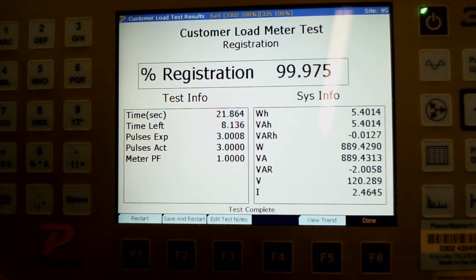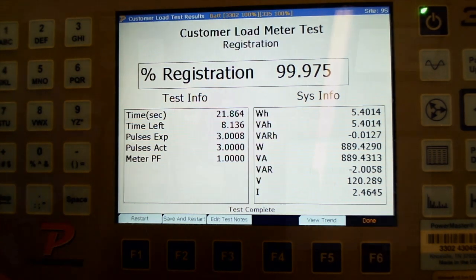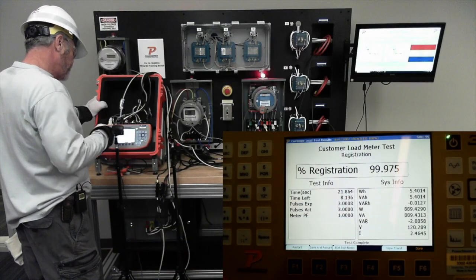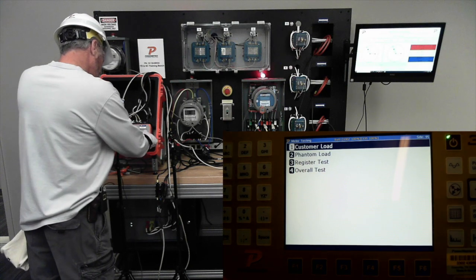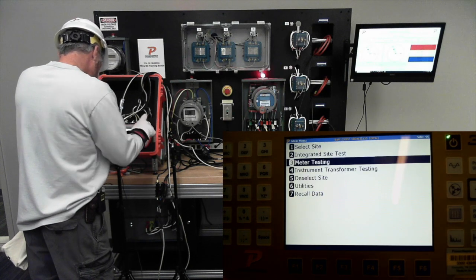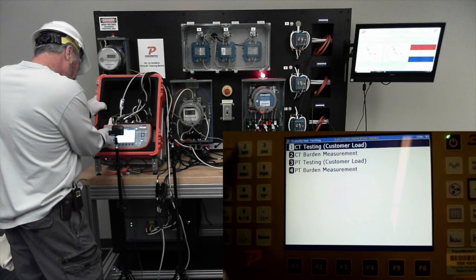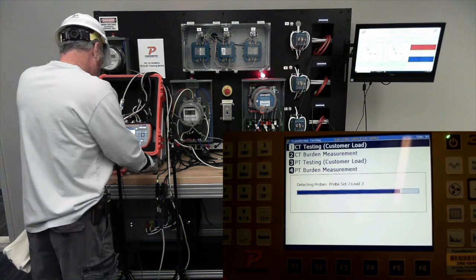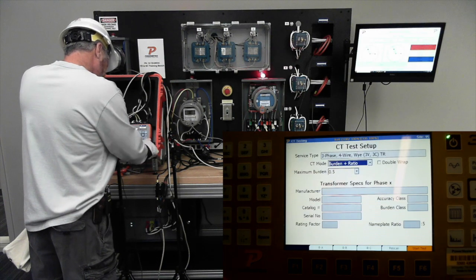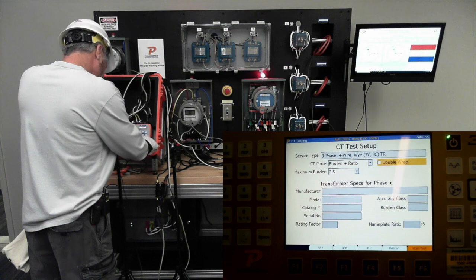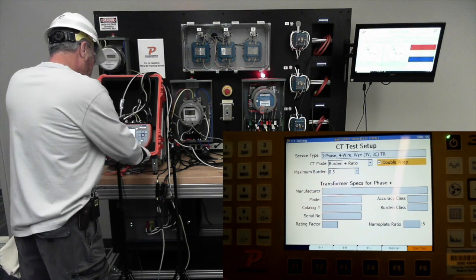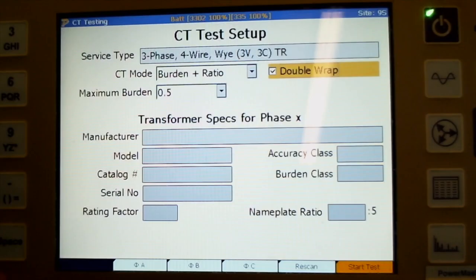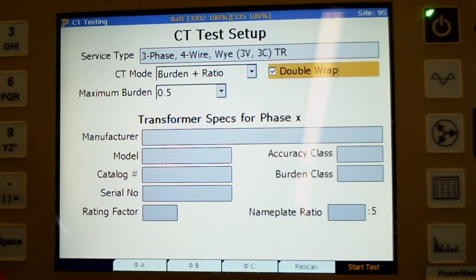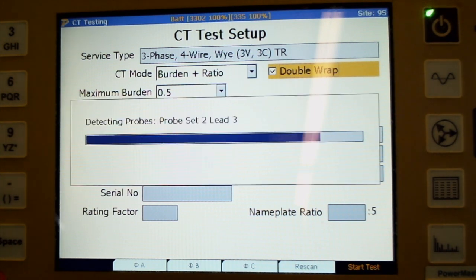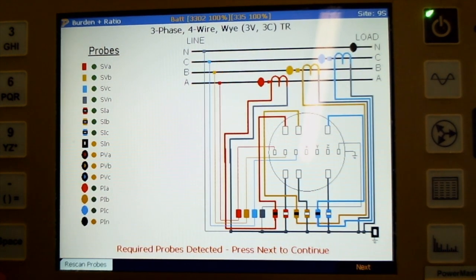All right, then we'll test our CTs real quick, and then we'll put an error scenario on there. It's one of the ones I like because it lets you use more functions on the test kit. So let's go to... make sure you check the double wrap box, right? Because I've got them double wrapped, or it's going to think they're 400s instead of 200s, or 600s instead of 3s—it'll double her up. So you got to check that double wrap box, and you can see I double wrapped them, so I had to check it. So we'll go next.